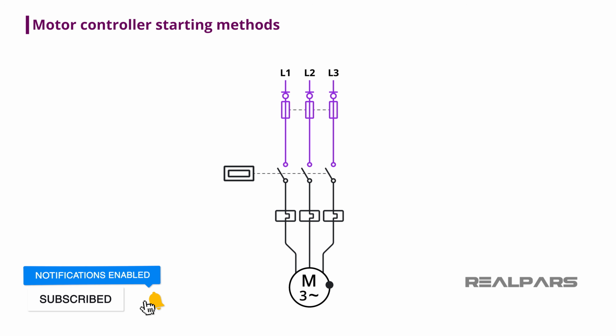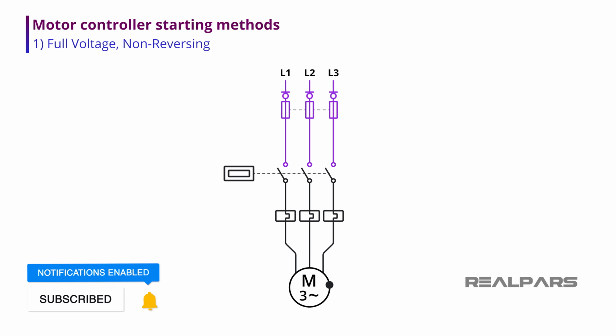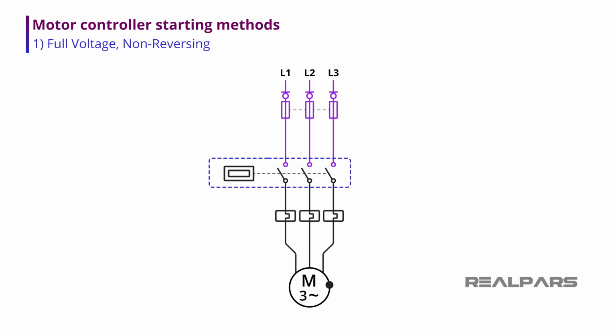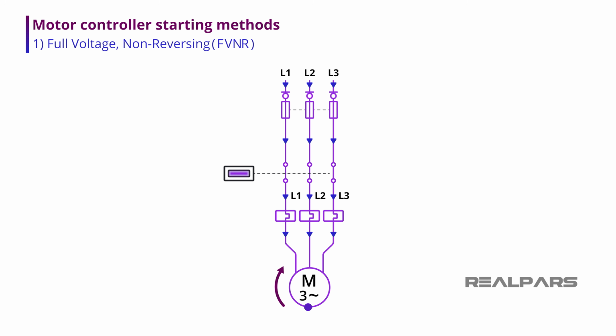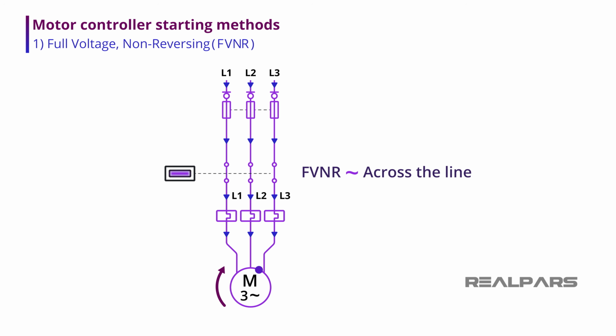The first starting type is the full voltage, non-reversing motor controller. As the name implies, when the controller's single contactor actuates, this motor controller type, also known as FVNR, allows the full-line voltage to pass to the motor. With an FVNR motor controller, the position of the line phases is fixed, and the motor can only be operated in one rotational direction. An FVNR can be thought of as an across-the-line controller.